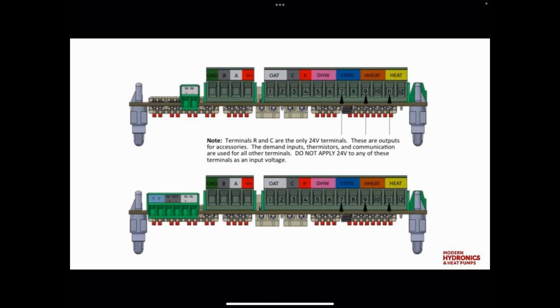Mhm. So one thing I didn't talk about when I was showing the ports on the back of the piece of equipment is there are motorized ball valves on each of the boiler ports. And so we can ensure that we have shut off all water flow, so we never run the risk of running any sort of chilled water through the boiler or having any sort of temperature migration and then have pipes sweating and that kind of stuff. So we've actually put motorized ball valves inside the unit on both boiler ports that are only active, of course, when we're calling for the boiler.